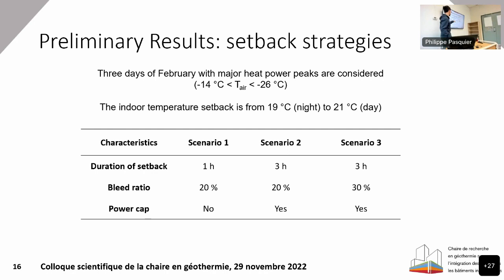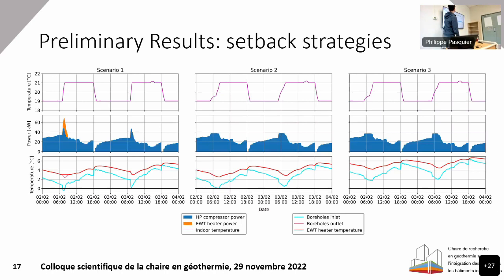And here you can see the preliminary results, let's say. You have three scenarios. Here you have a fast transition in 1 hour. Here you can see that it's much smoother, in 3 hours. And in the second row, you have the power. In blue is the heat pump compressor power, and in orange is the auxiliary resistance power.